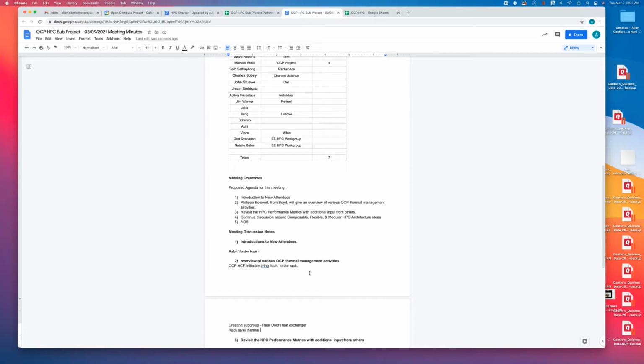There is the Open Rack version 3, the new rack, and it has now an option to have an RPU, a pumping unit, to circulate liquid within the rack. There has been a definition of a manifold, like a liquid bus bar that runs along the back of the rack from top to bottom, bringing cool liquid to each server and extracting hot liquid from each server connected to the pump.